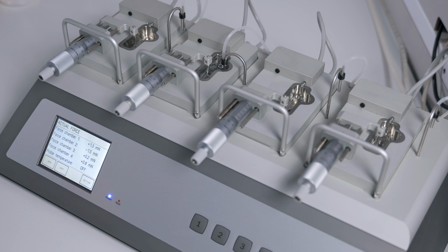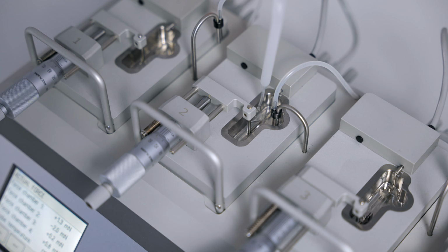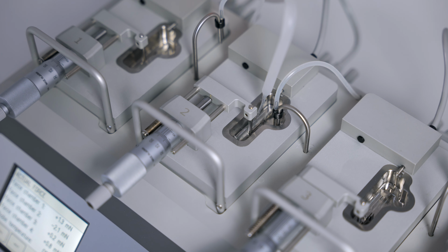If a hydrophobic reagent was used, the first steps might not be enough to properly clean the chambers. You can use 96% ethanol or a weak detergent solution. To clean more resistant or toxic chemicals, fill the chambers with 1 molar hydrochloric acid for 1 to 2 minutes. In the most severe cases, we would recommend using 3 molar nitric acid for no more than 2 minutes.